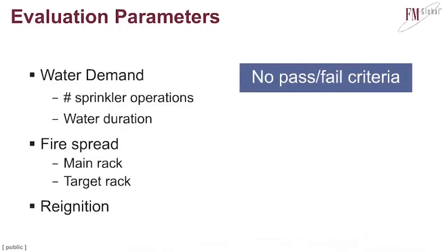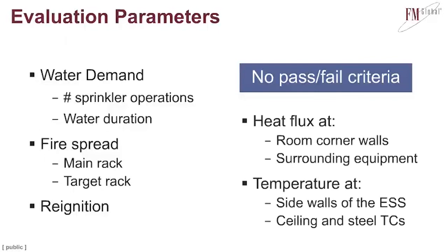It's really important here to realize that I'm not trying to actually provide a pass-fail evaluation for these tests. Okay, this is more trying to understand what the hazard is and what type of steps we need to take to bring that hazard down to an acceptable level if that's necessary. So that's really where I'm going to rely on my heat flux data. So how much heat are you pushing from the fire to the room corners or to the walls, to surrounding equipment that you may have nearby, and also the spread of the fire from one rack to the next, which is what we'll be looking at, all the different temperature measurements that we have.